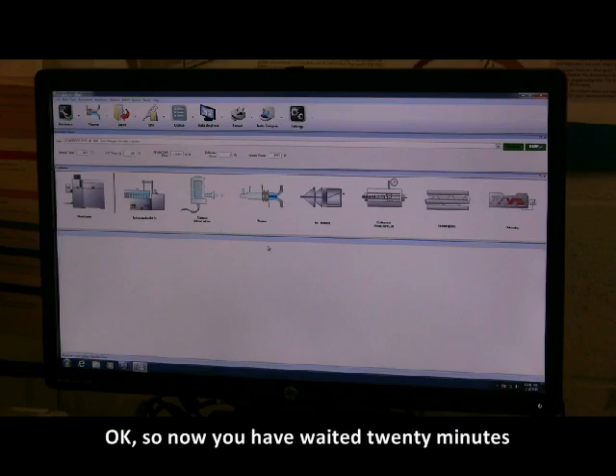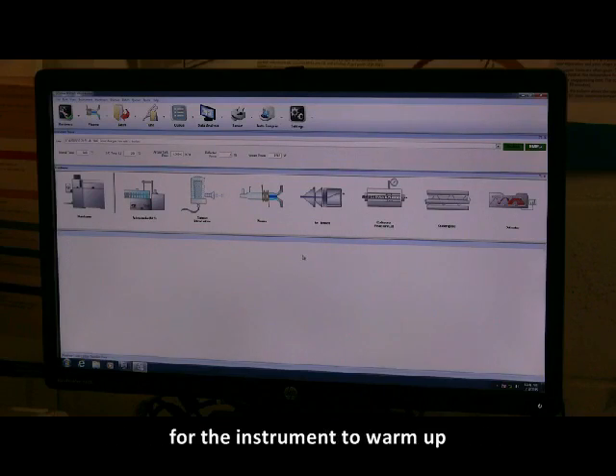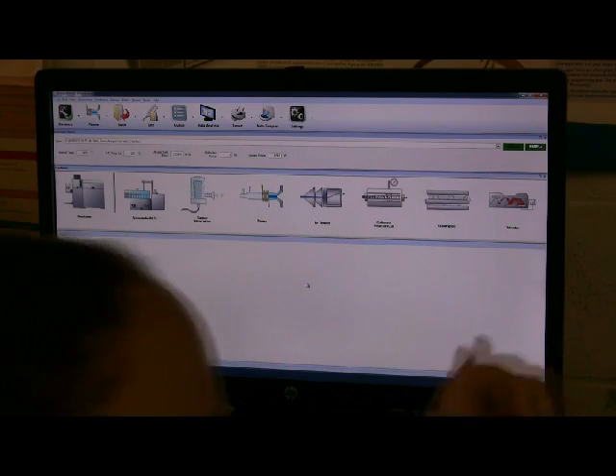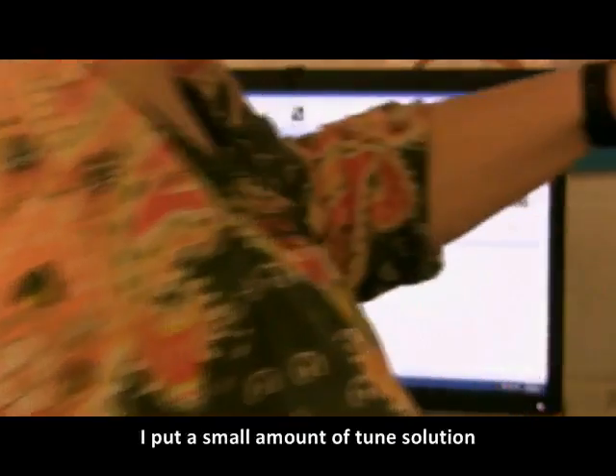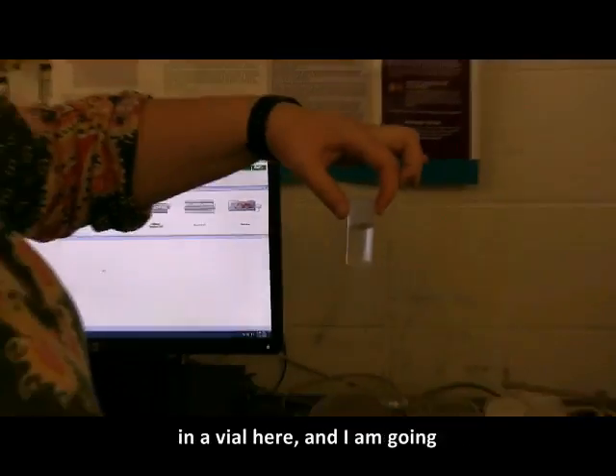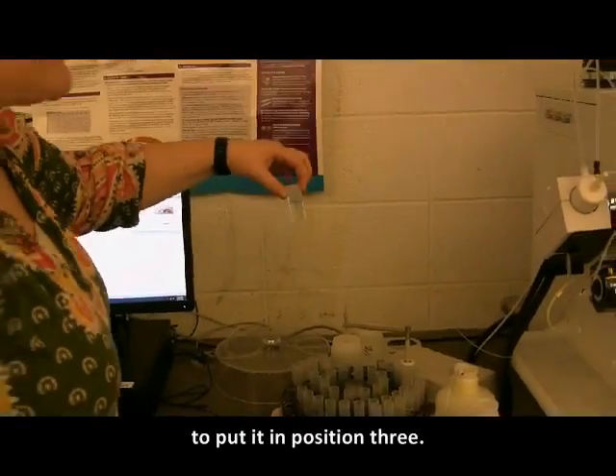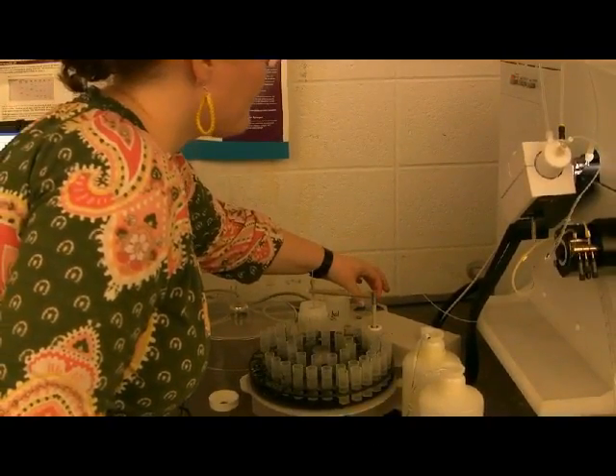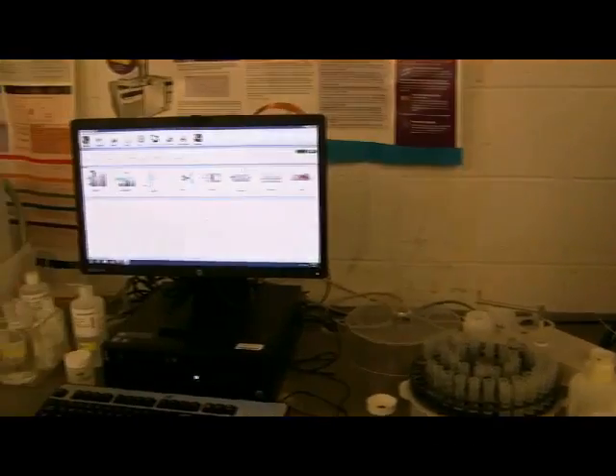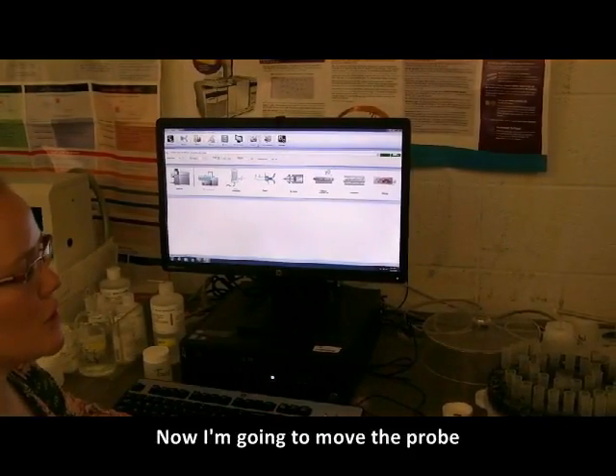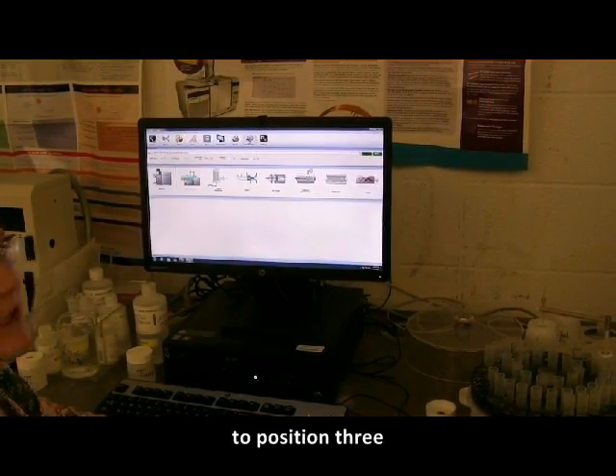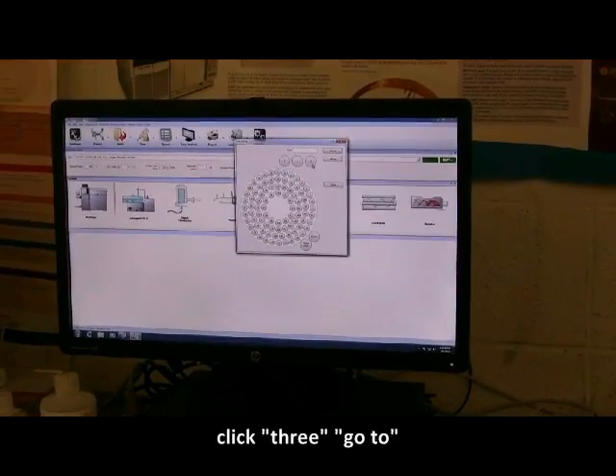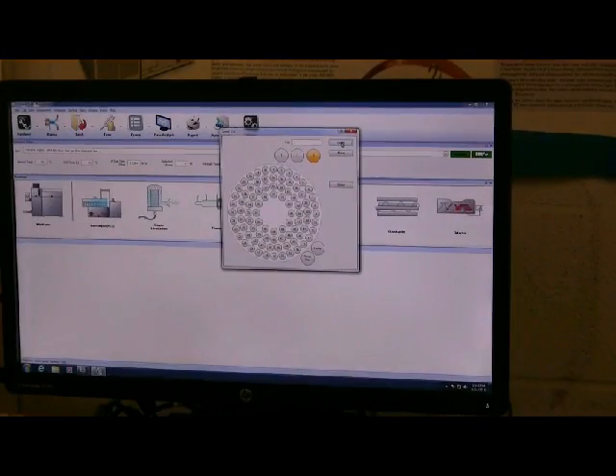Okay, so now you've waited 20 minutes for the instrument to warm up, and the probe is in DDI water, so now we have to tune the instrument. You have to tune every single time before you run. I put a small amount of tune solution in a vial here, and I'm going to put it in position 3. Now I'm going to move the probe to position 3, clicking on the big autosampler button, clicking 3, go to.